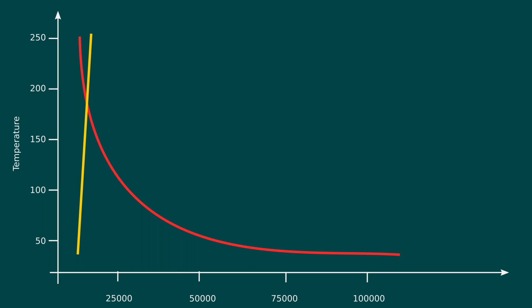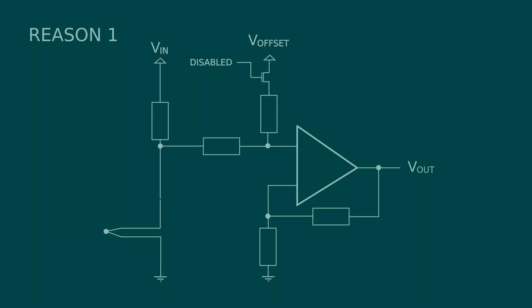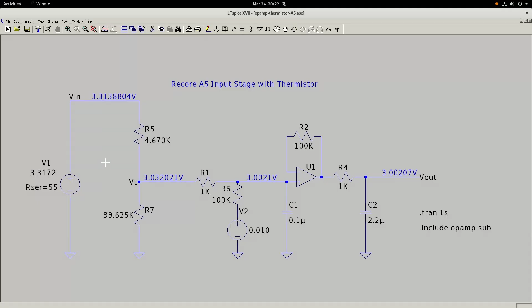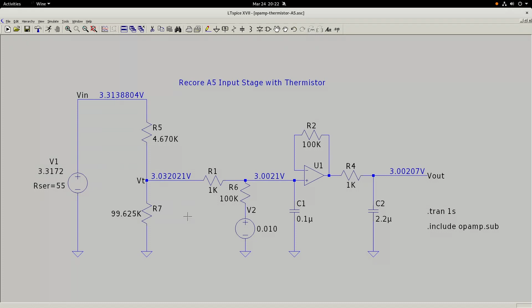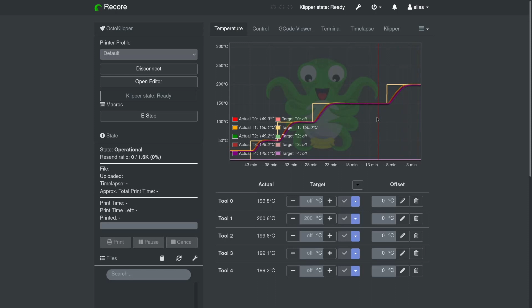As I discovered, the reason for both errors was twofold. Reason 1. In order to use the input for both thermistor and thermocouple, a fixed but programmable offset was added to the input. When turned off, the offset should not influence the measurement, but it did. The impact was easy to model in SPICE and then transferred to Klipper. The results show a slight improvement, but even with this issue out of the way, the temperatures were still off.